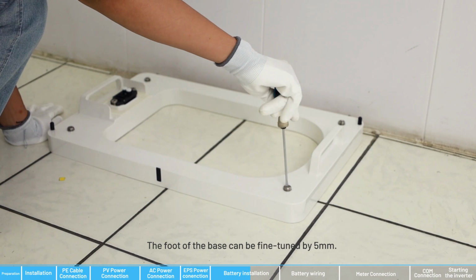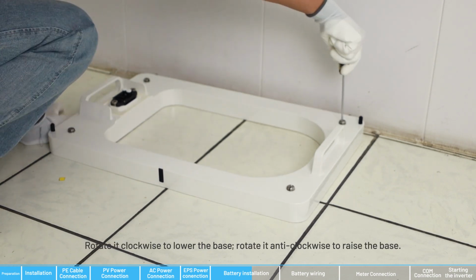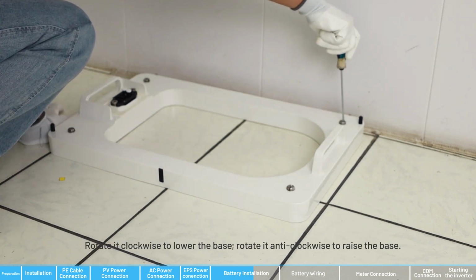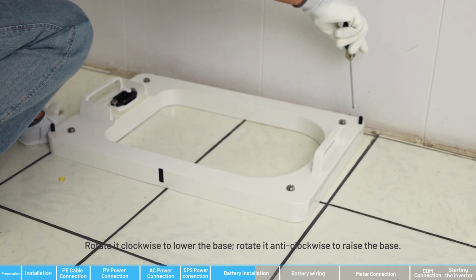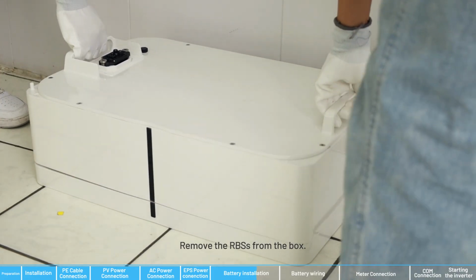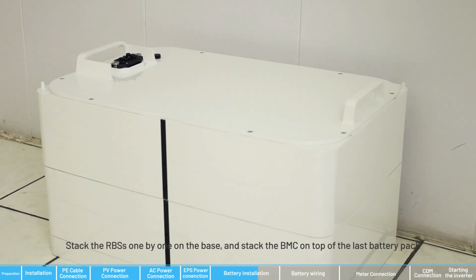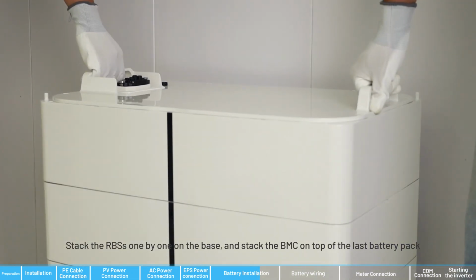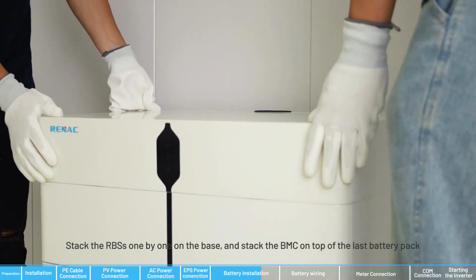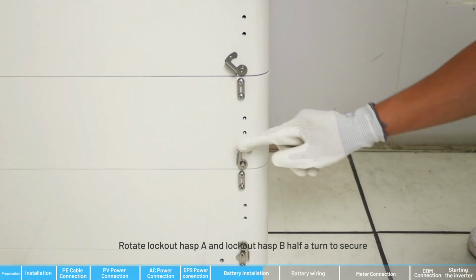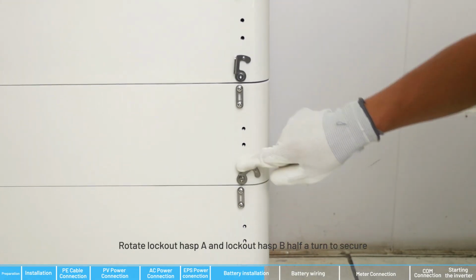The foot of the base can be fine-tuned by 5 mm. Rotate it clockwise to lower the base. Rotate it anti-clockwise to raise the base. Remove the RBSs from the box. Stack the RBSs one by one on the base, and stack the BMC on top of the last battery pack. Rotate lockout hasp A and lockout hasp B half a turn to secure.